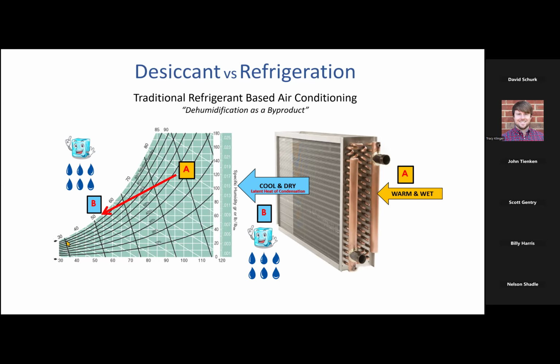Right? Now, the problem with that is simply that if I have chilled that air so far that when it is put back out into the space, it creates an uncomfortably chilled space, then I have to do something to that air to warm it back up. I've removed the moisture, that's great, but I now have to add sensible energy to this air and maybe warm it from 40 up to 55. So I've got 15 degrees of reheat, right? And that can be very inefficient and unsustainable if I'm using new energy to provide reheat. So that's a problem with regards to this type of system, a cold coil system.